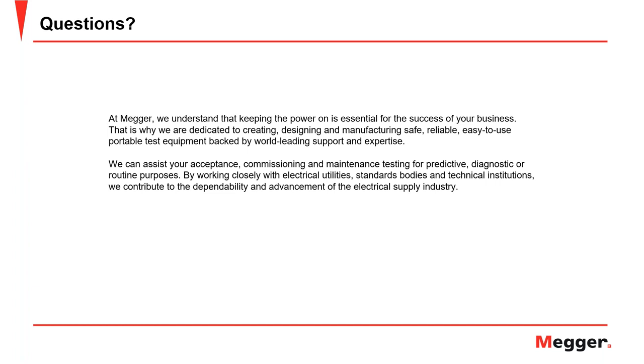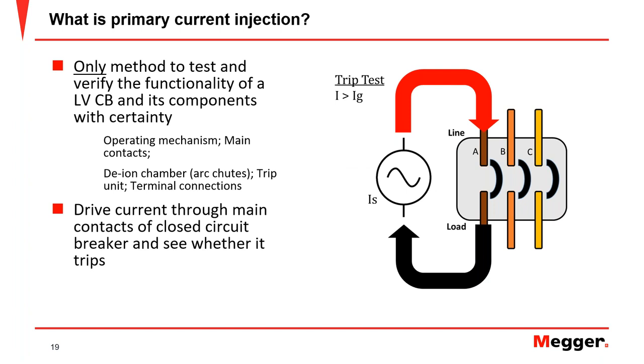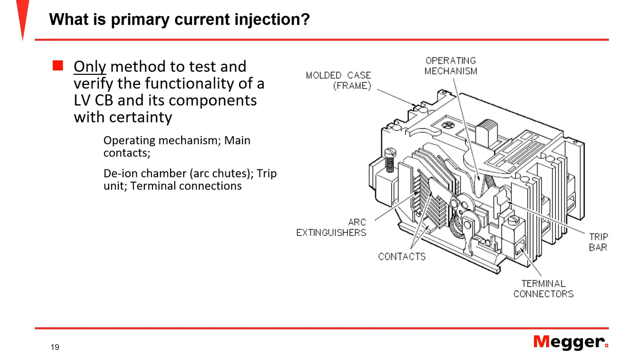Question to Daniel: when testing, is it acceptable to test one phase to verify the brains are working, or should you run the full test on all three phases? Daniel recommends running the test on all three phases. While each measurement does verify the trip unit, there are other elements on each individual phase that are involved — including the terminals, the main contacts on each phase, and the sensing elements (the CTs). You want to make sure all of them are in good working condition, so it is always recommended to run measurements on all three phases.